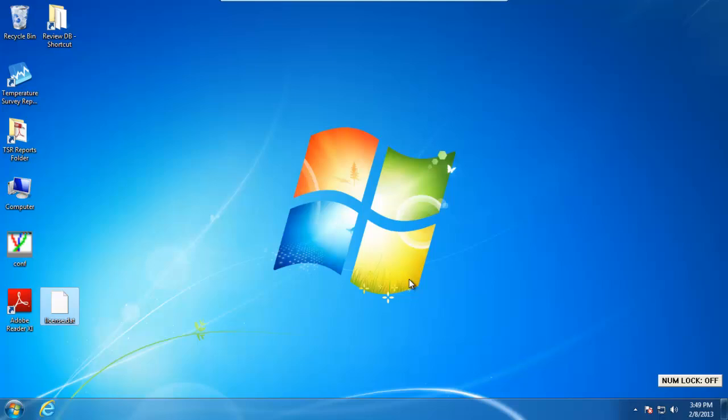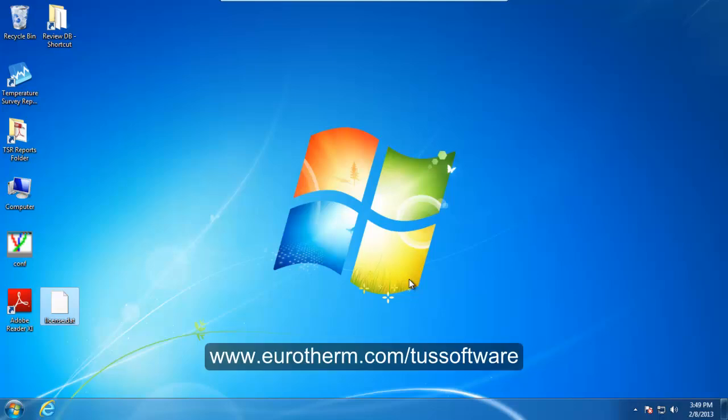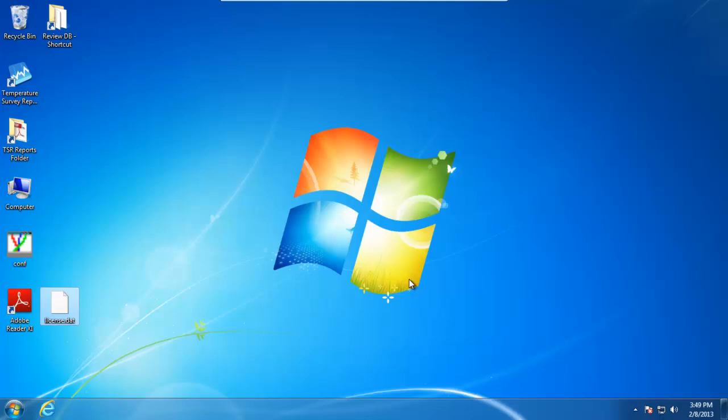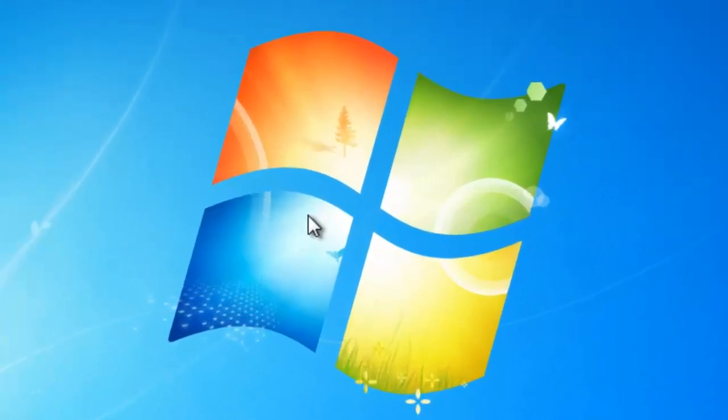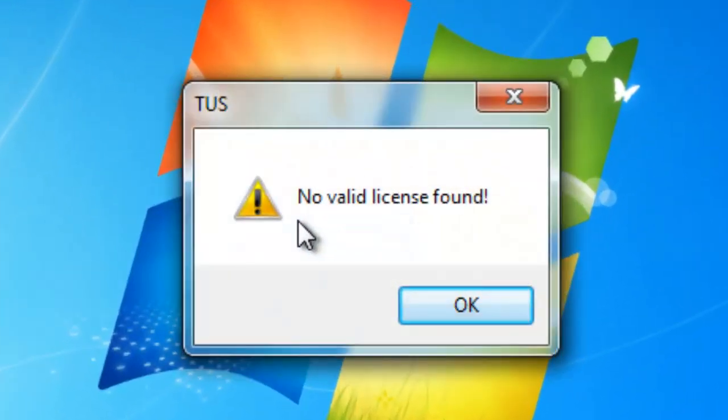This instructional video is going to cover generating a TUS report using Advanced Eurotherm's temperature survey report software. Now, assuming you've gone to our website, Eurotherm.com/TUS software, and have downloaded the software, we're going to assume that you're opening this up for the very first time. So whether you click the icon on your desktop or underneath your start menu, when you open it up, you're going to be presented with a box that says no valid license found.